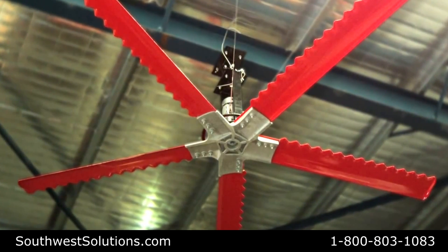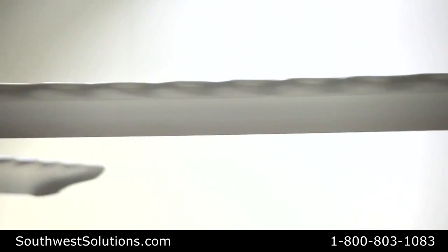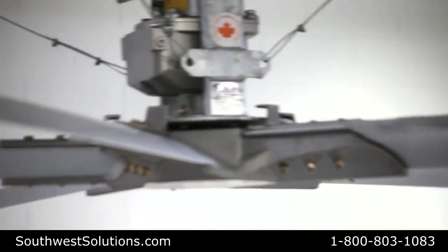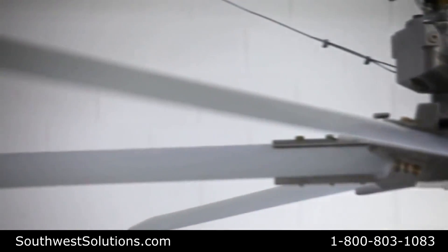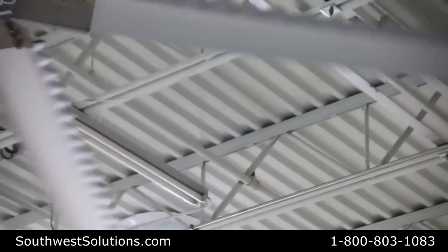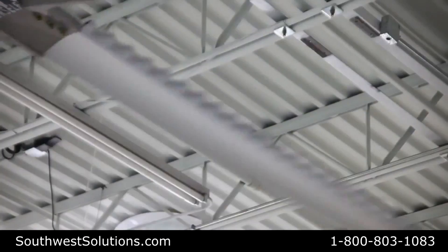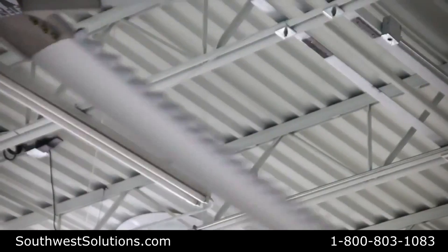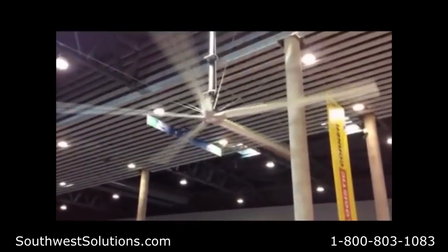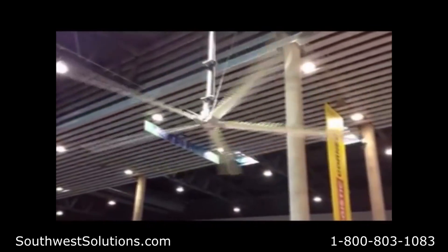When doing a direct comparison between the tubercle bladed fan and the airfoil fans, there are a number of important features that stand out. Performance: the tubercle 16-foot diameter reversible high-velocity low-speed fan with a 1.5 horsepower motor is capable of producing 182,173 cubic feet per minute. The 16-foot diameter airfoil fan with a 1.5 horsepower motor only produces 162,231 cubic feet per minute.